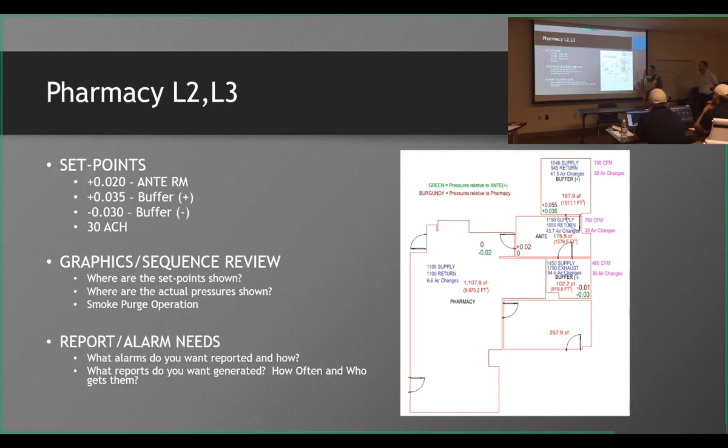Sometimes that could lead us to a little bit less fluctuation, because when we open this door, the air rushes out of this room. And then these two are trying to catch up to it. So that's why these pharmacies were so tough to balance, right? We got them under control. They're pretty delicate, quite honestly, right? Plus they have powered fan filter units, yeah, which is not helping things. So anyway, it's important that you guys understand how it's set up and how it's represented.